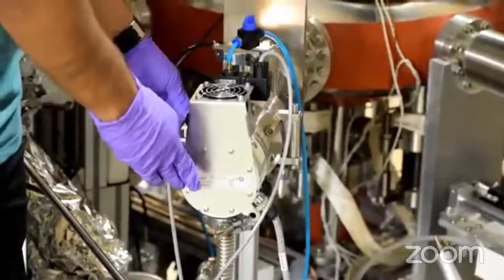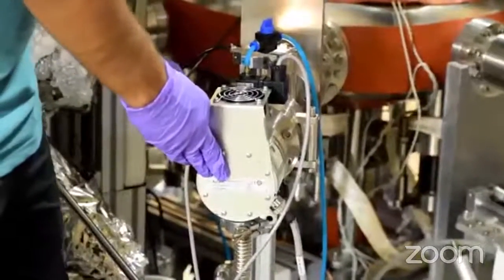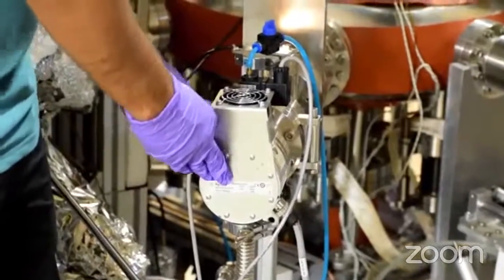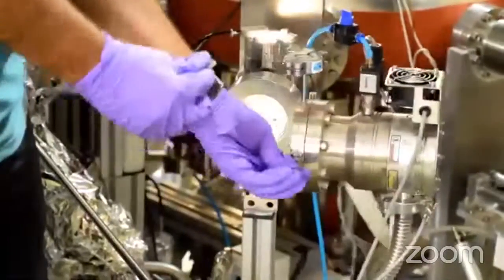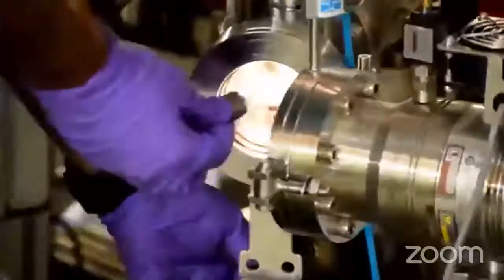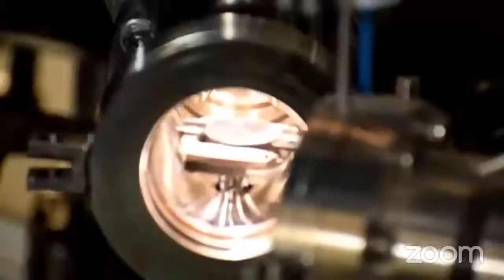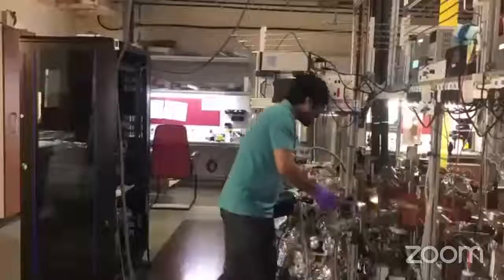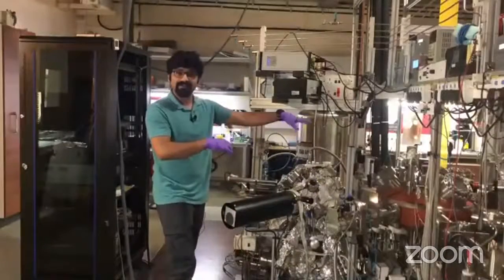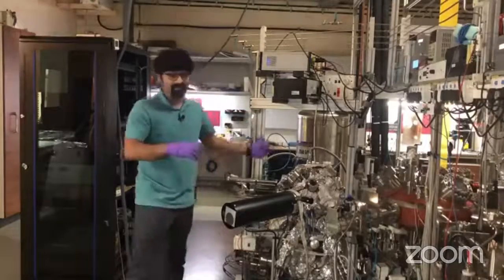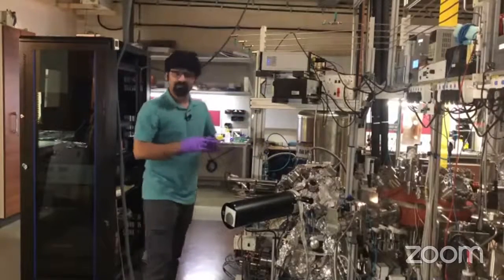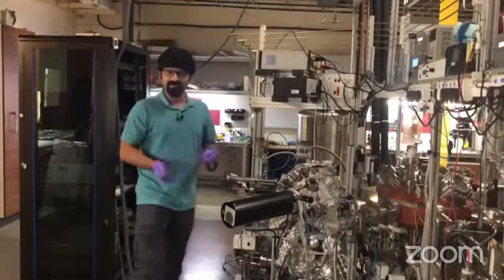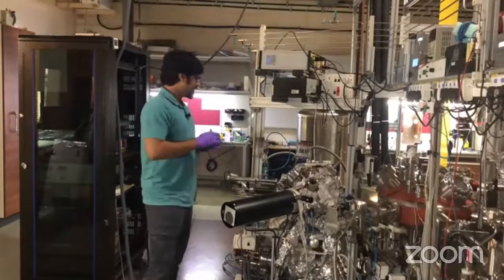And this chamber is a small one, so it's relatively easy to pump it, and this can be done without breaking the vacuum of other chambers. This is how the journey of a sample starts. And then it has some mechanical arms, which you can control, and it can move to the MBE. Now, inside the MBE, you can deposit these materials by evaporating them, and the way you evaporate is basically just heat it up and let it boil, just like water boils.